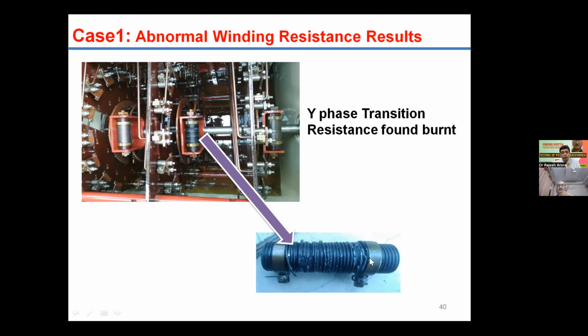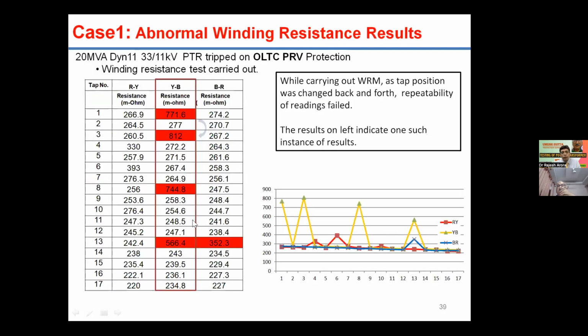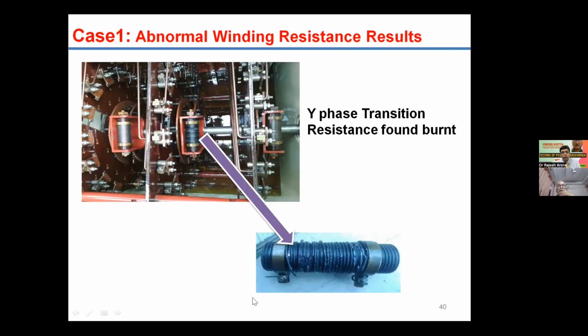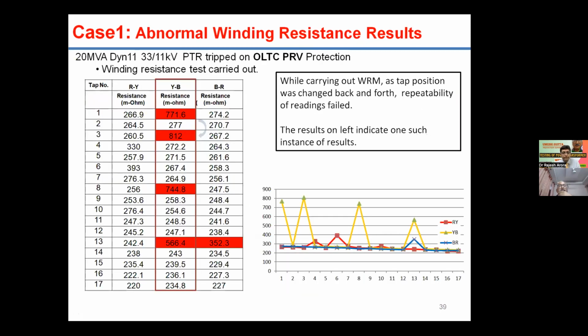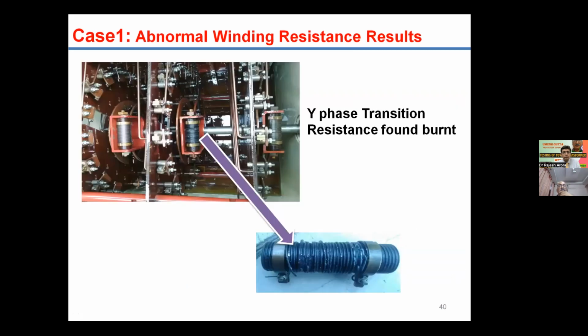You can see the strands have got damaged and we were getting an abnormal pattern of winding resistance. So the overhauling of this transformer was done at site only. This resistance was changed and alignment was corrected. And thereafter, we received proper results.